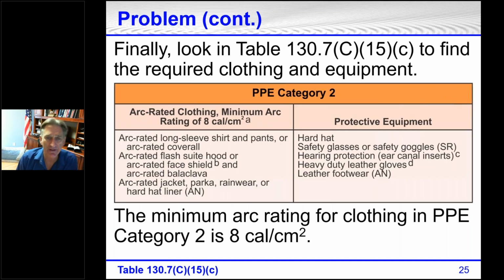We finally look at table 130.7C15C for what we would have to wear. Remember, on the previous slide, it showed a category 2. Category 2 has to be at least 8 calories per square centimeter. What can they wear? Arc-rated long sleeve shirt and pants, or arc-rated coveralls. Some industries and plants have daily wear arc-rated clothing. And arc-rated clothing has gotten so much better over the years. I've got a shirt in the closet that is one of the first arc-rated shirts, and it's 8.7, which was pretty high, really good at the time.